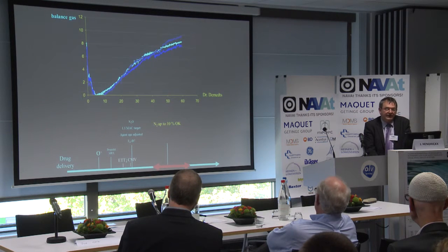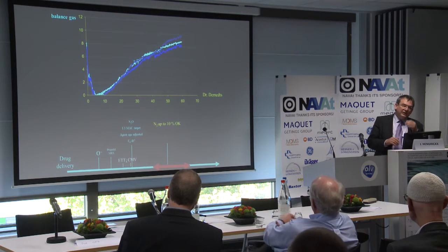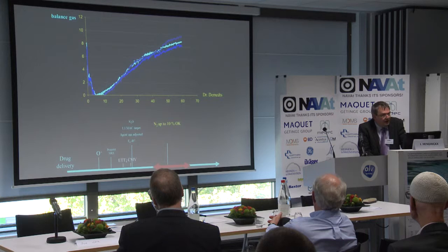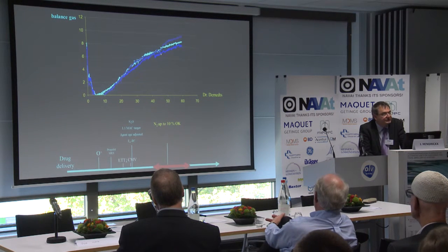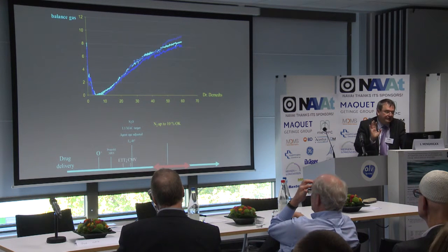And it's actually okay to let it rise. I think it's important to let it rise because it allows you to use really low fresh gas flows. And these are data from Robrecht De Meyts here, still to be published. You can see that over time, the nitrogen will rise slowly over 60 minutes to 10%, but that's okay.